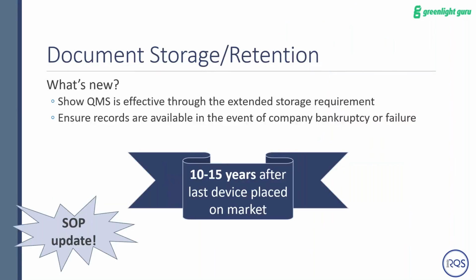Some new things on document storage. Now they're saying that 10 to 15 years after the last device has been placed on the market, you have to maintain your documents for that device, all your documentation. So all your records, your quality control records, your UDI records, all those have to be maintained. This is where the idea of electronic document control and storage, and a lot of what Greenlight's doing a great job of, is really, I think, essential if you want to comply with this.